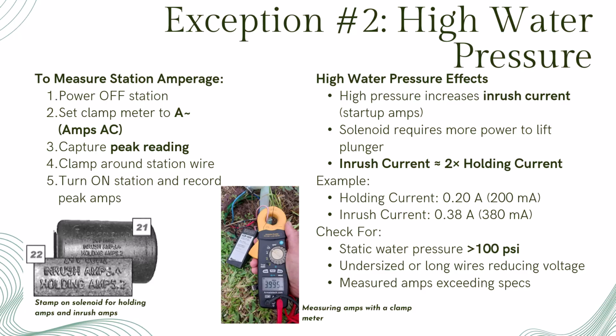For example, if the holding current is 0.2 amps, the inrush current might be around 0.38 amps. When pressure climbs above 100 psi, or if the wiring is too small or too long, the available voltage may not be enough to meet that higher demand, and the valve may fail to open completely.